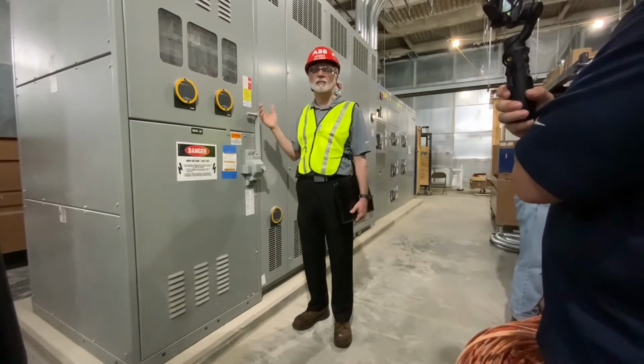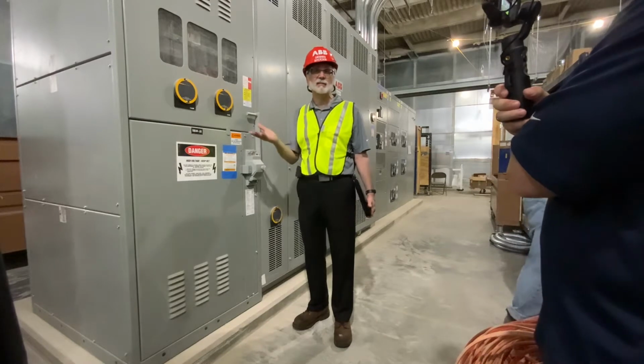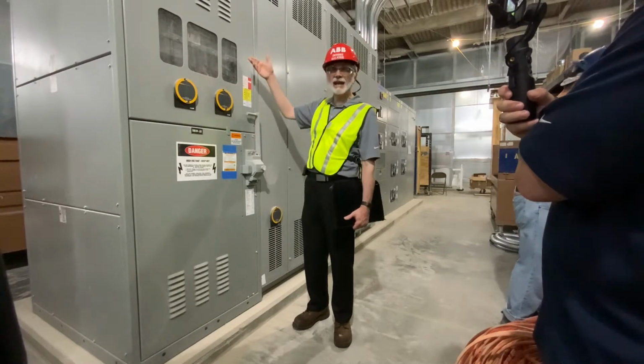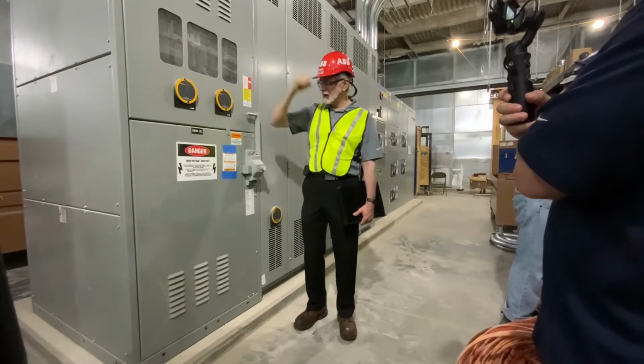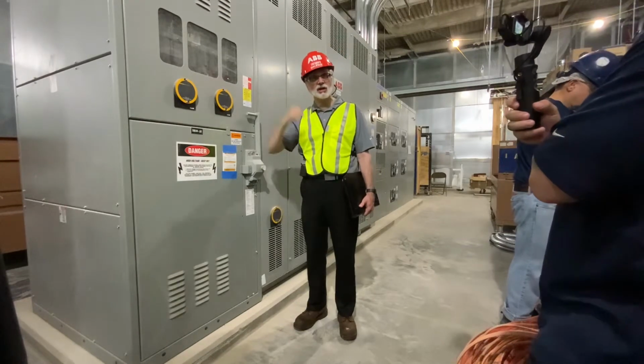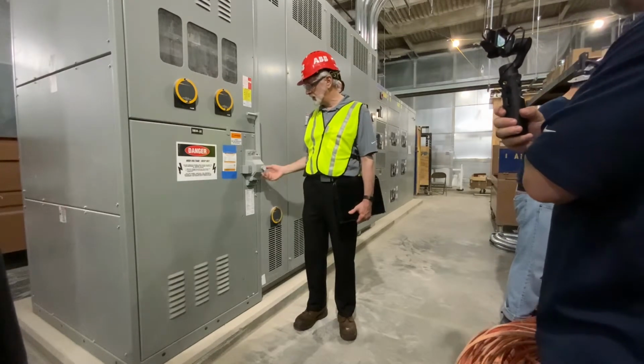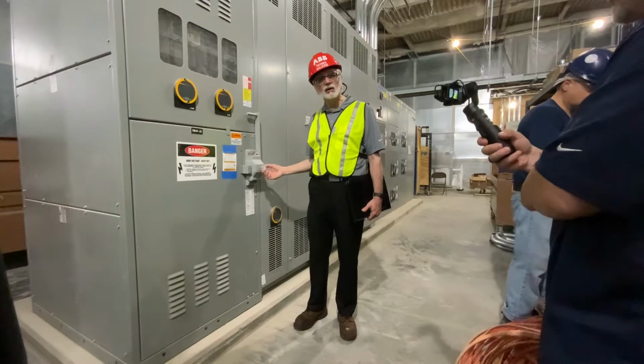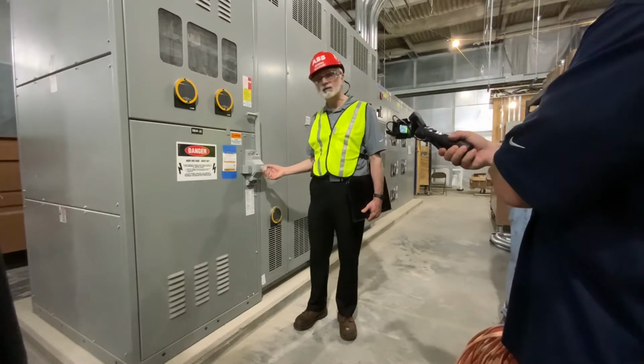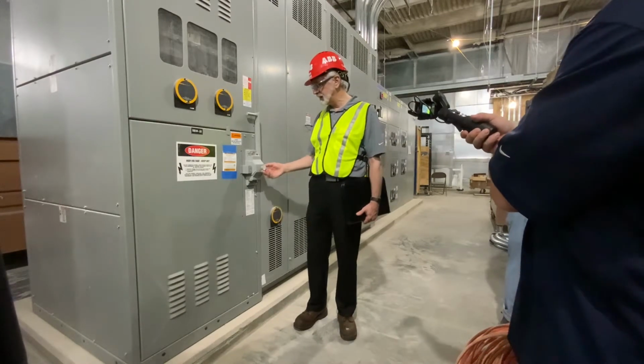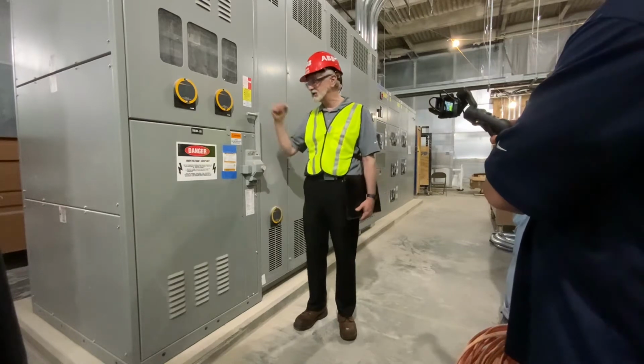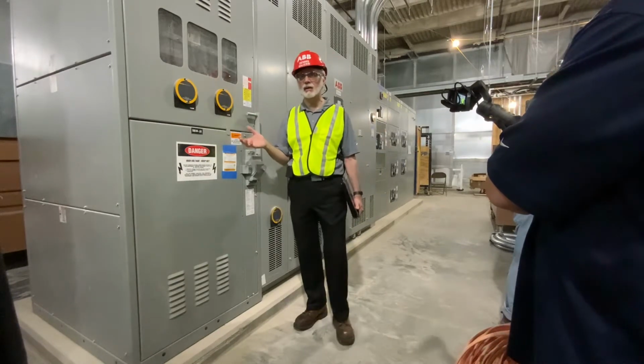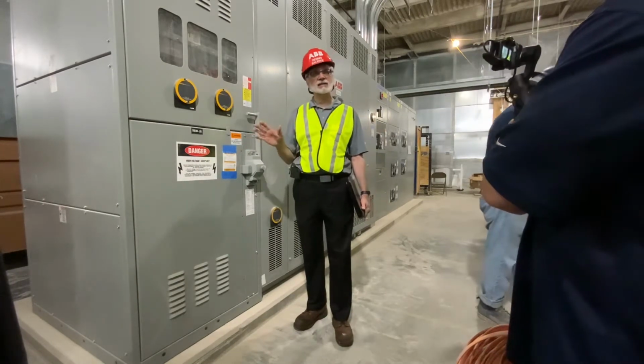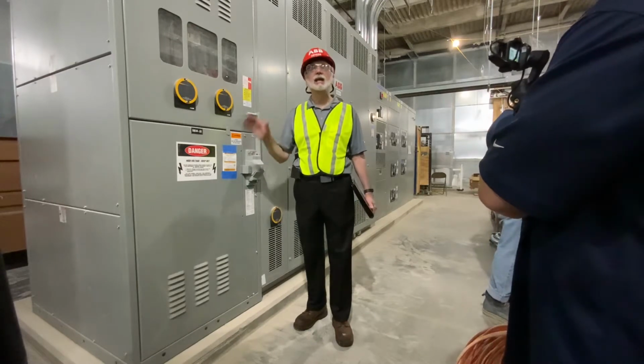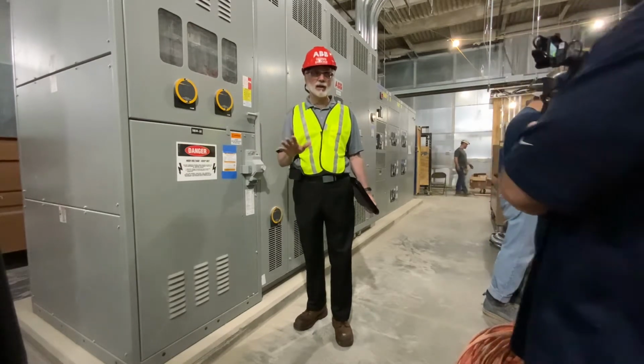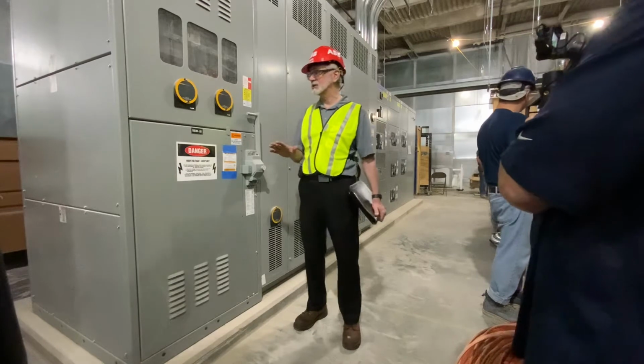This is a very basic piece of equipment. It's sort of like a medium voltage safety switch, probably the best way to describe it. I've got cable connections in the back, and then I've got a quick make, quick break switch here to operate and open it. To operate the switch, there's a little safety bypass that has to be pulled out before you can change the position of the switch. It is quick make, quick break. We're not going to go into the details of the operation because, again, this is something that should be done by a qualified medium voltage electrician.